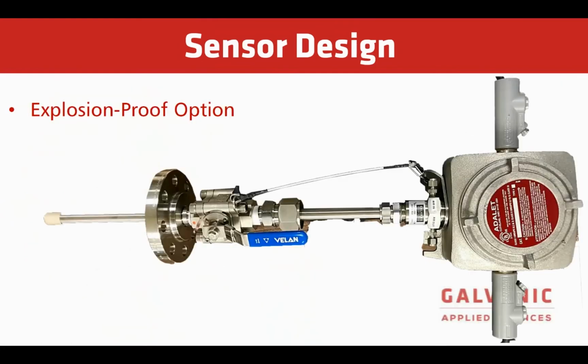Here's our standard Class 1, Div 1, Div 2 installation sensor design. Again, has the ball valve. This one looks like a 300-pound, 2-inch or 3-inch flange. So that will attach onto a port in a sample pipeline. This one also has, for higher temperatures above 100 degrees C, if you look just below the enclosure, that enclosure has an air in and air out. That is an air purge for the cooling tip to keep the tip from getting too hot.